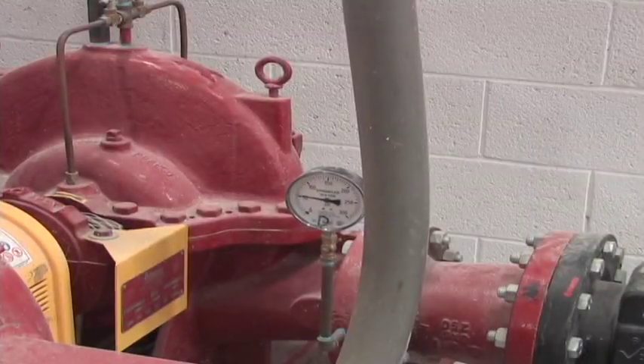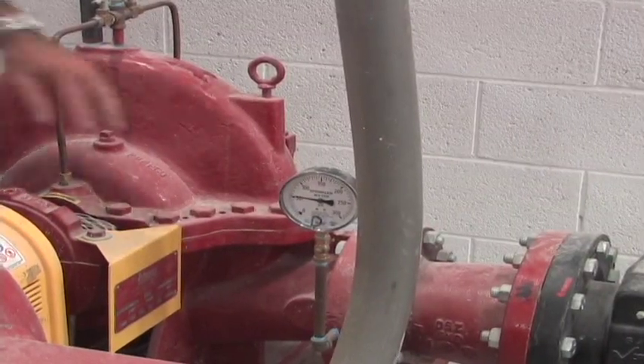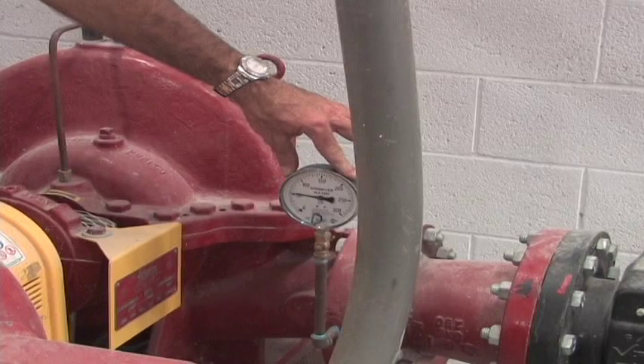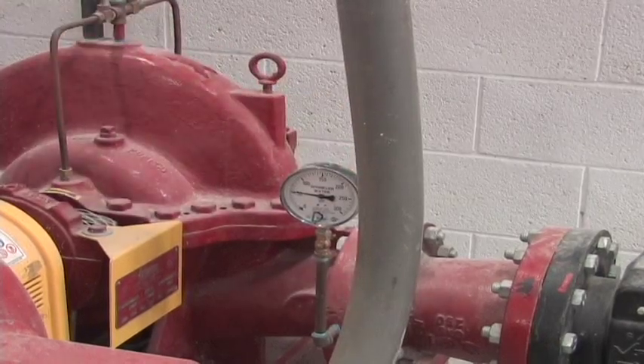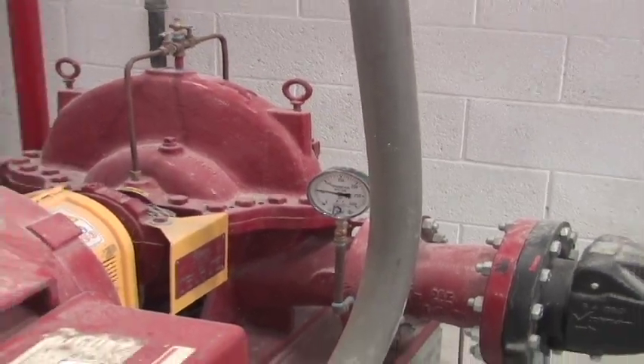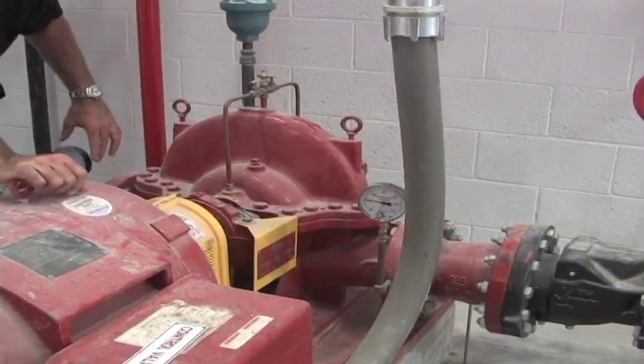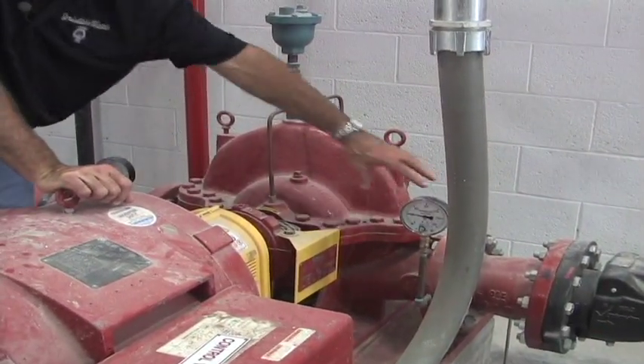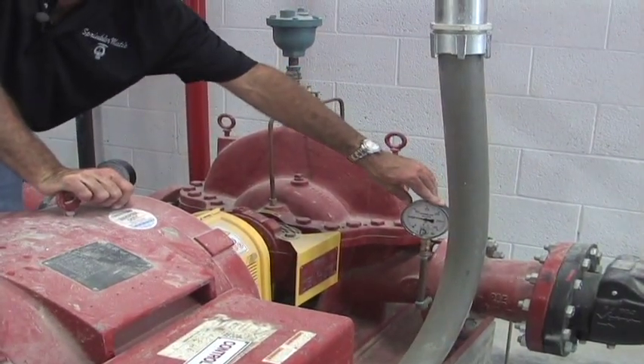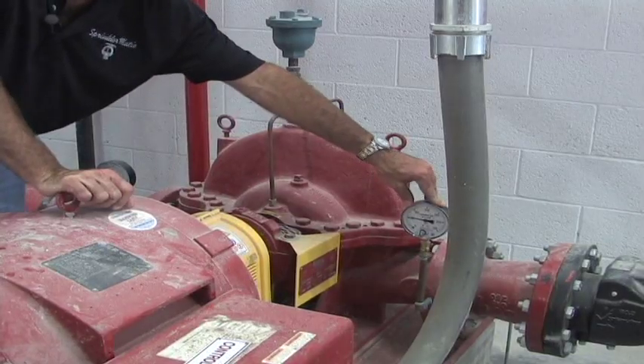Again, this is going to be our suction pressure gauge, and this will be our discharge pressure gauge. Both of these, when the pump is not running, will be at the same pressure. Of course, when the pump is running, our supply is going to be the same, and our discharge will be up to whatever the pump churn is, roughly about 190 psi.